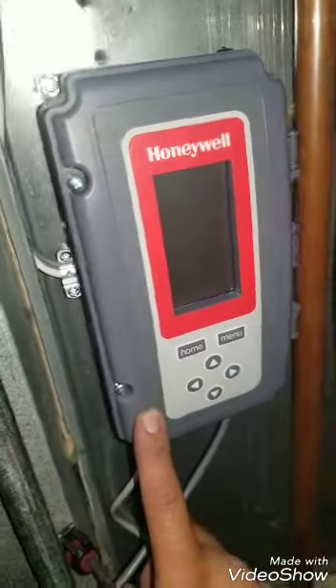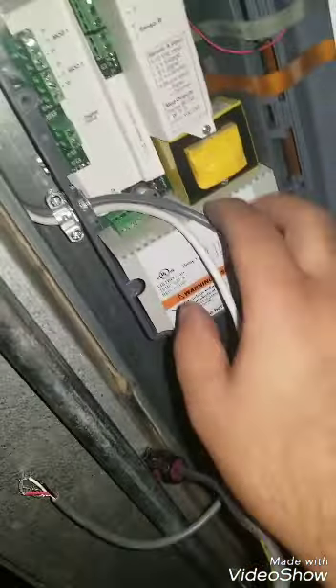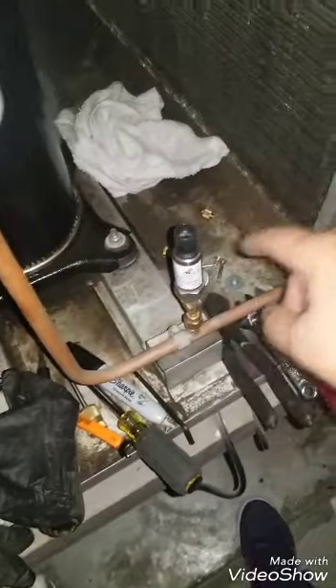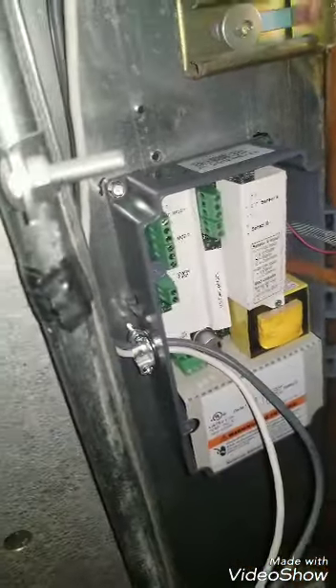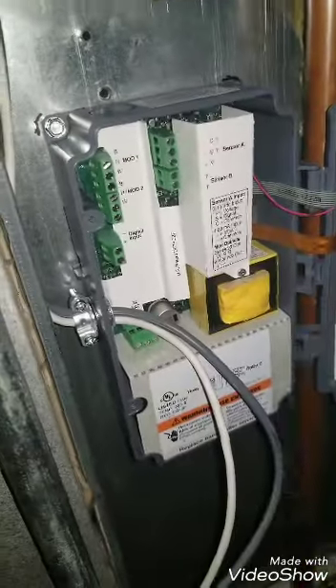Step 6. Mount the T775 wherever you're going to put it. Step 7. Run your low voltage wire that's going to your transformer through your panel, up, over, and down to your T775, which is gonna go right there. And then this gray wire is from your transducer. Transducer goes right there, goes up, and joins the wire over here. Last, take your Belimo wire, poke it right through the hole, and you're almost done.